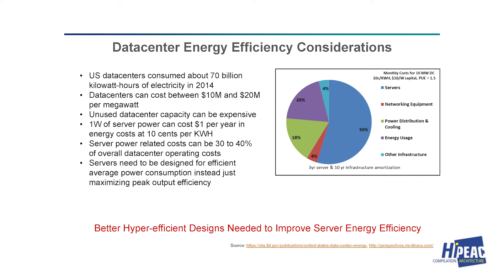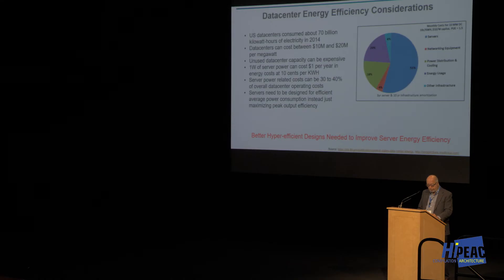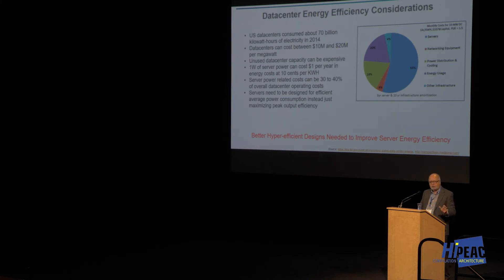The green segment is depreciation on the capital to construct the data center for power and cooling, and the purple is actual energy consumption cost. This is based on a 3-year life; if you go to a 5-year life the acquisition cost stays the same and these pieces get even larger. Unless you design your servers for energy efficiency, you need to look at efficient average power consumption — not just the maximum power — and use all of the power that you paid for.